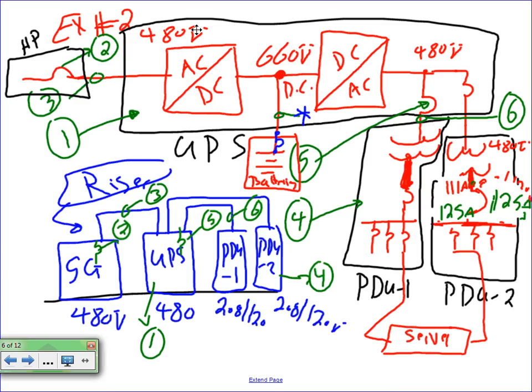In Revit, we were not able to find a UPS with a transformer. That's why I asked you guys to do it this way. In real life, the transformer will actually be part of the PDUs. The PDU itself will have a transformer. Can you see the transformer here that you looked at? That transformer in real life will be in a box with the PDUs. They have one big box that takes the voltage here, 480, transforms it to 208/120, and distributes it to all the loads.